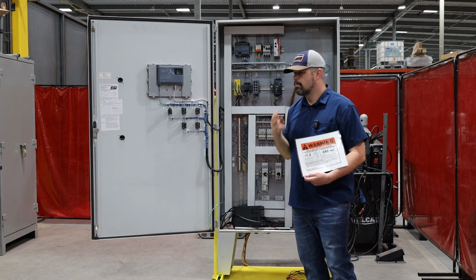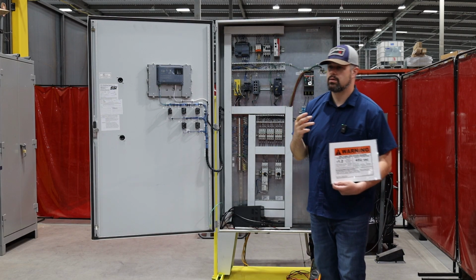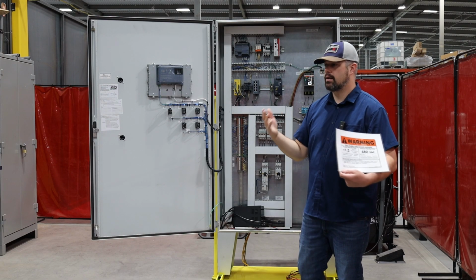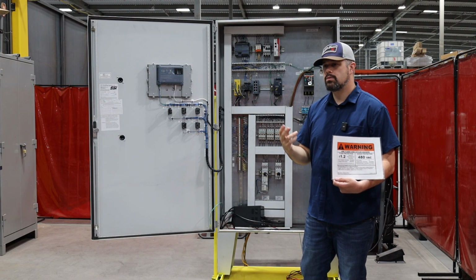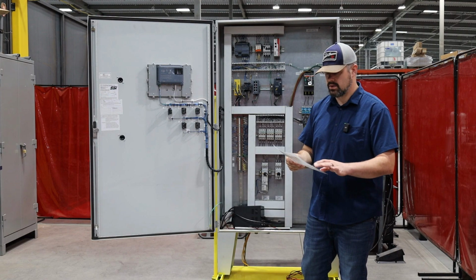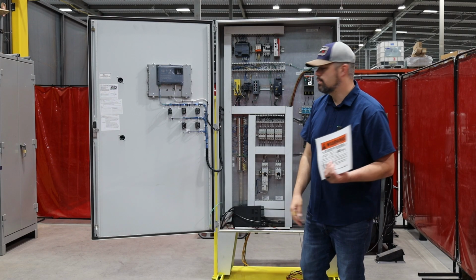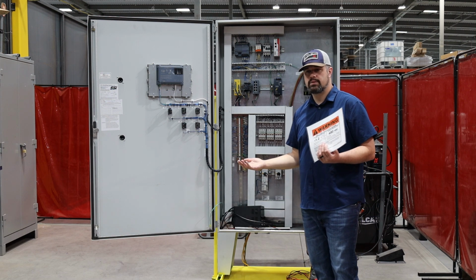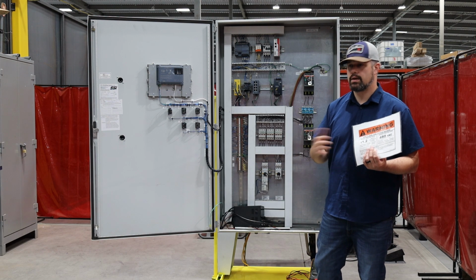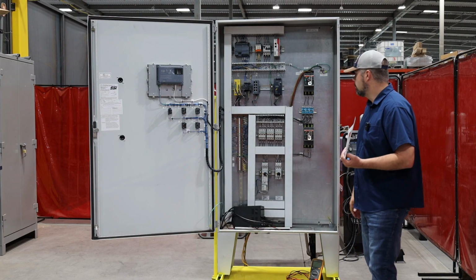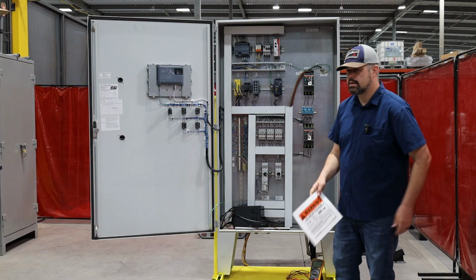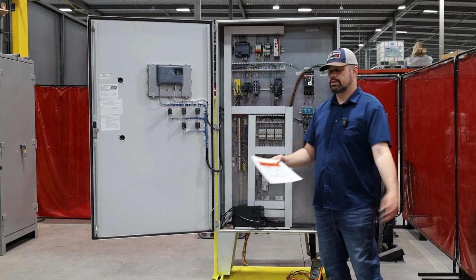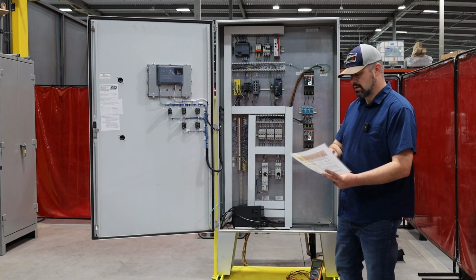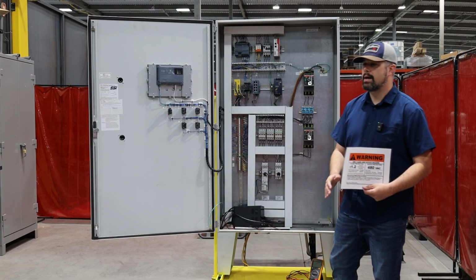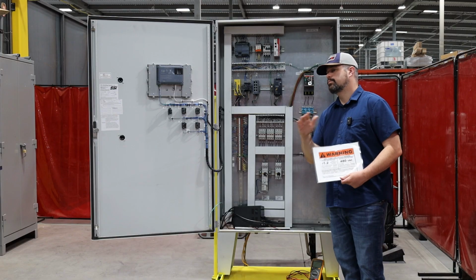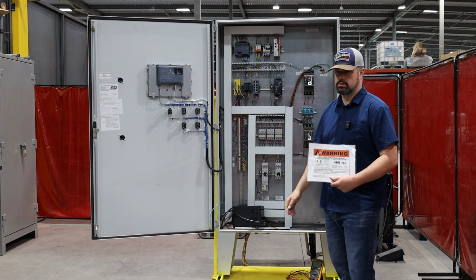This is why I say a lot of 70E comes down to 3 main things. 1, being able to create and understand an electrically safe working condition, right? 2, being able to read and interpret correctly everything on this label. And 3, being able to correctly perform live-dead-live, so you know for sure something is in a complete zero state of energy. Once you know how to read these and understand this, it's all about the boundaries. 18 inches, or whether it's the limited approach boundary. Once you know those boundaries, now you can apply that simple knowledge to a whole lot of different scenarios, right?